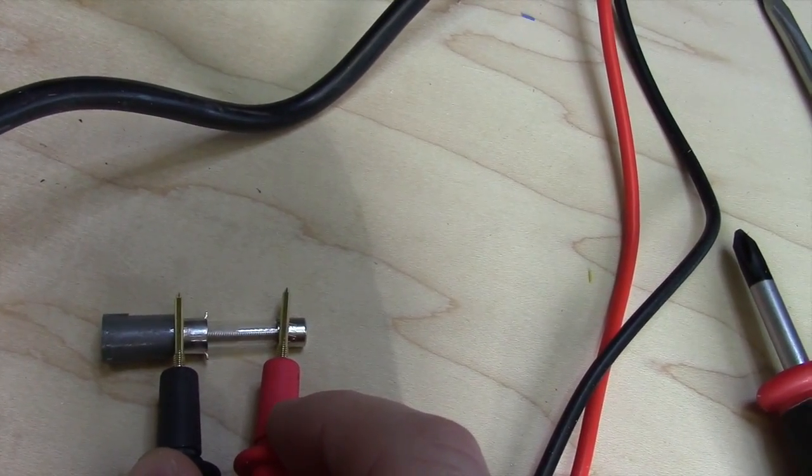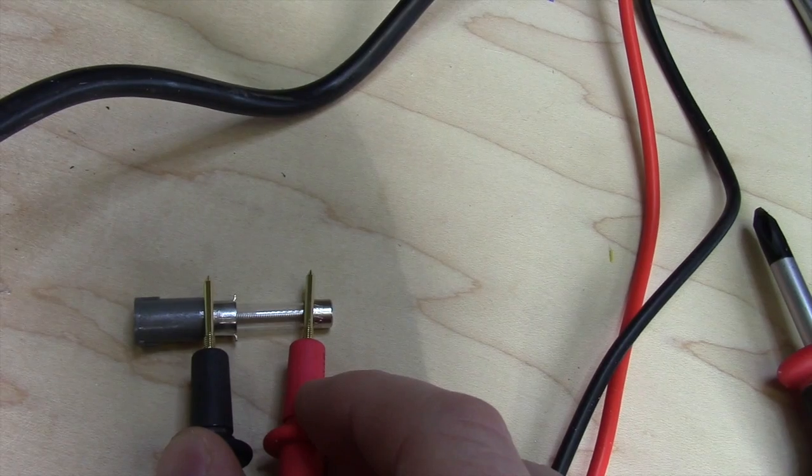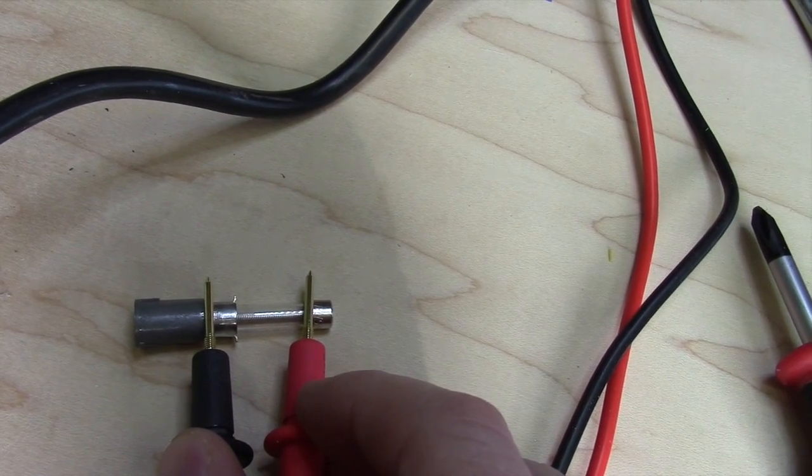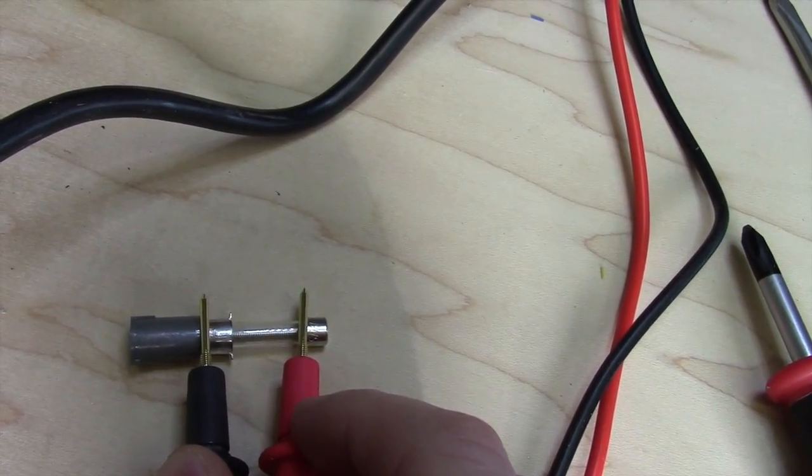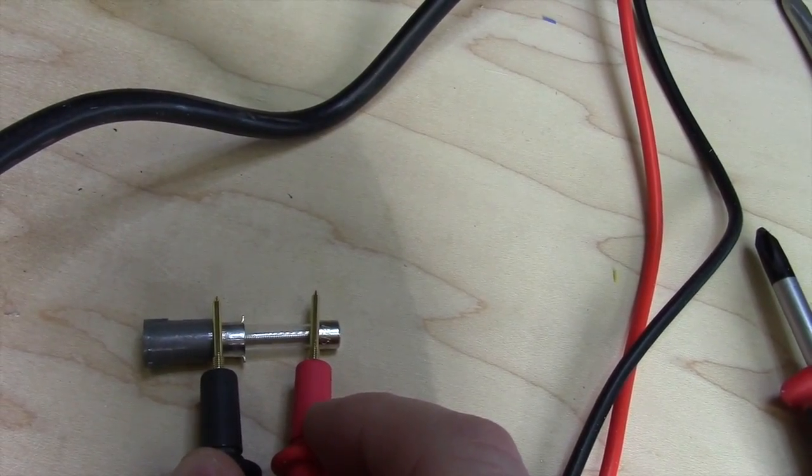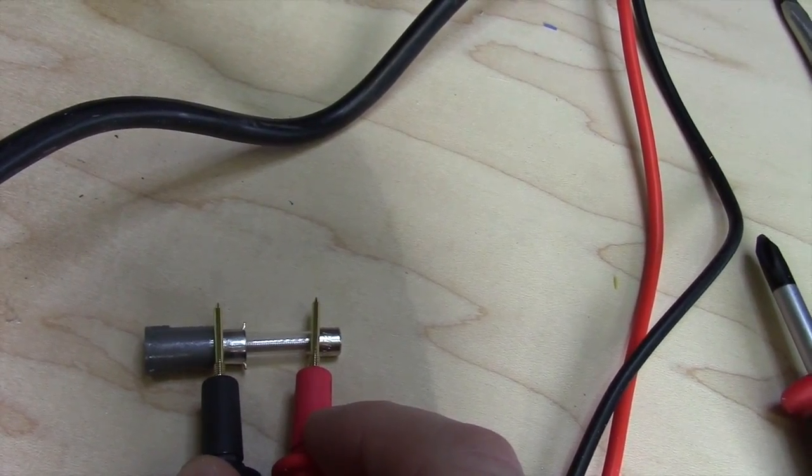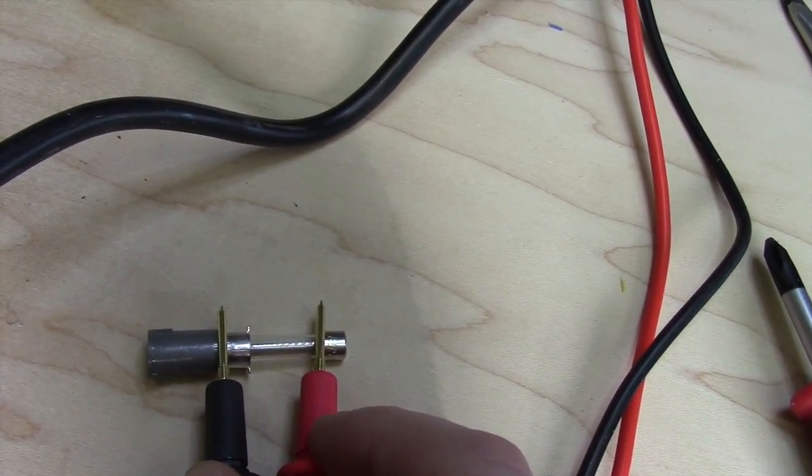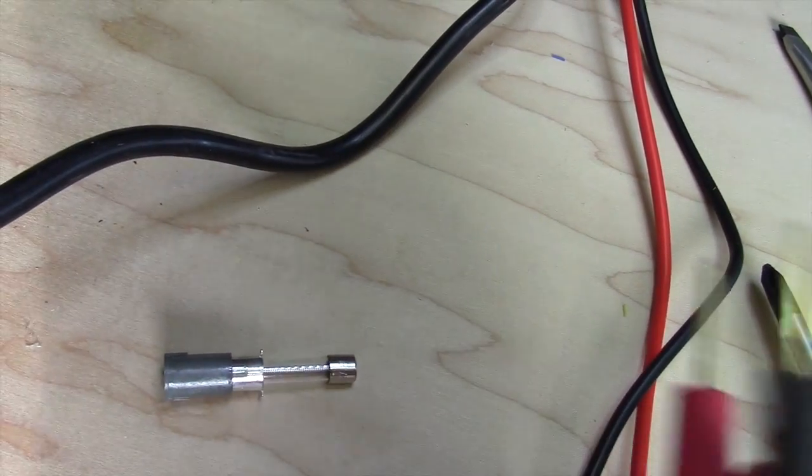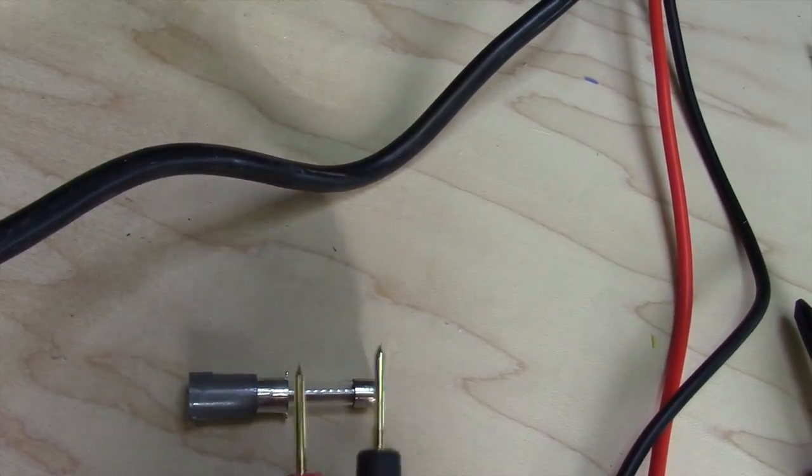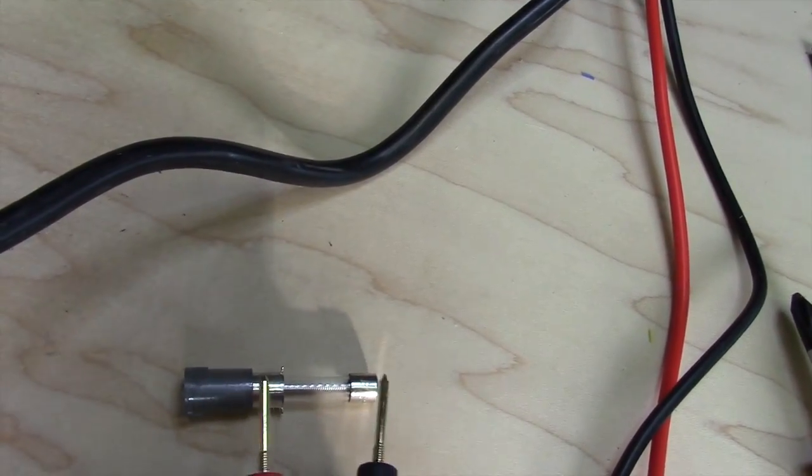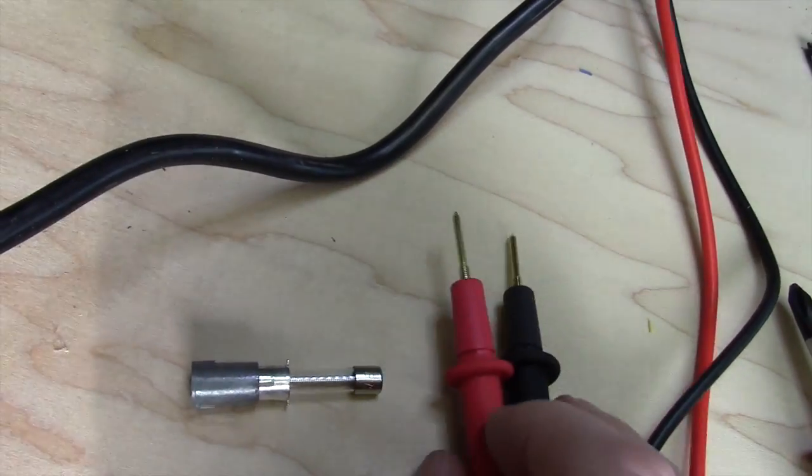And no, the fuse is not the issue. This fuse is perfectly fine. Like I say, it's one of the easiest things to check, but also if the fuse is blown, something's caused that to happen, and you should really check to make sure what the actual issue is. What has caused the fuse to blow to begin with before proceeding.